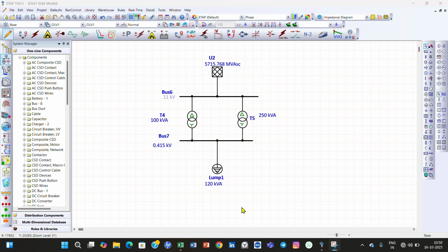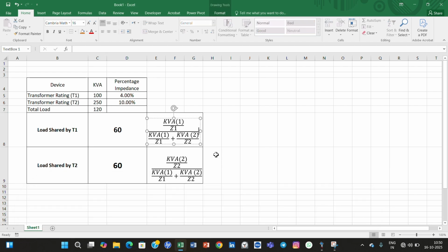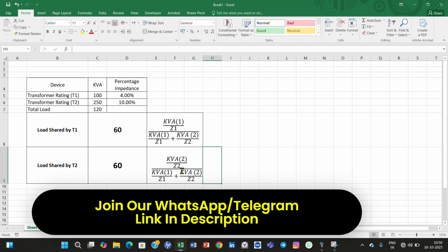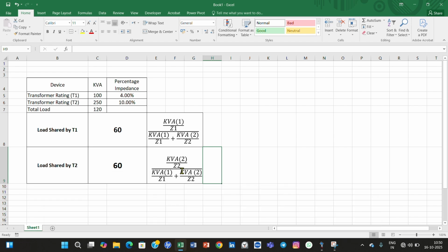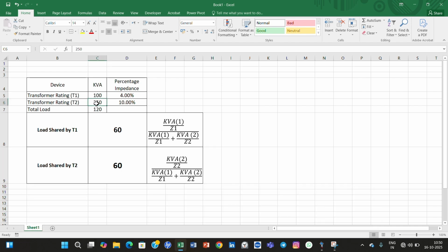First of all, these are the two formulas which we have studied in BTech, this formula and this formula. As per these formulas, we can calculate the load shared by different transformers when they are supplying a load in parallel. First, we will take a 100 kVA transformer and a percentage impedance of 4%. You can see the load shared by transformer 1 is 60 and by transformer 2 is 60. Now we will keep these transformer ratings and percentages in ETAP and see what the load share is.